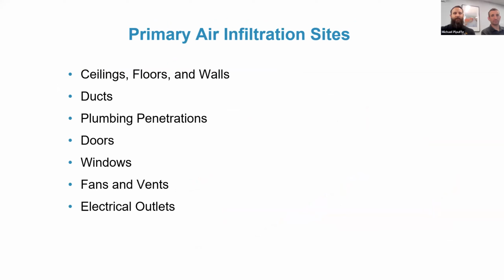In terms of air infiltration, most of the areas that I identified in the previous slide contain places where you should be very focused on minimizing where any air can move uncontrolled: along the ceilings, floors and walls, including plumbing penetrations, anywhere wiring is being run, and open cavities that may not have been sealed up when the building was constructed. Any operable doors or windows, or inoperable units that should be sealed up, as well as forced ventilation systems. All the ductwork on HVAC systems should be properly sealed so that the conditioned air is actually delivered to where it's intended to be, versus leaking into unconditioned spaces.